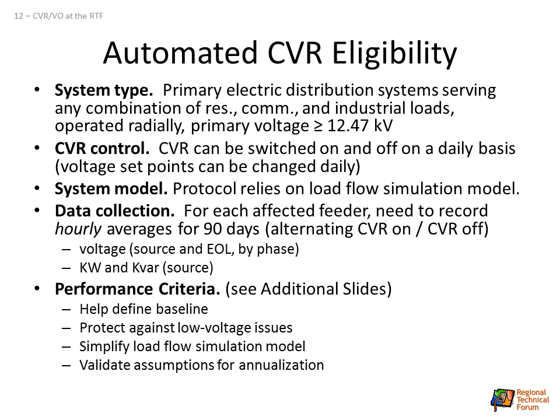The data collection requirements here: for each affected feeder, hourly values for 90 days, alternating CVR on, CVR off. Voltage, that's source and end of line by phase, power and reactive power, just as source for those two. Performance criteria are spelled out in the additional slides, and the reasons for having them are similar to the simplified case.